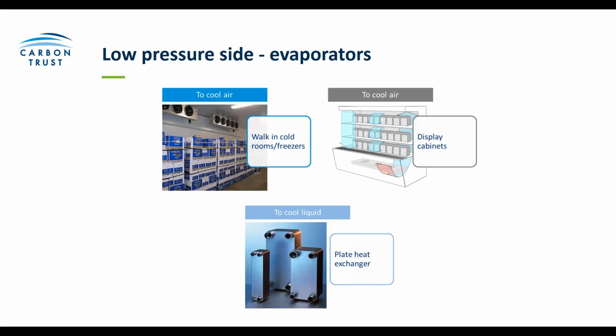So on the low pressure side of things, these are the evaporators. So this is the area where the thermal energy will be collected from the local environment, and the refrigerant is evaporated. So to cool air, you'll usually see walk-in cold rooms and display cabinets cooling air, and in terms of cooling liquid, you'll normally see plate heat exchangers.